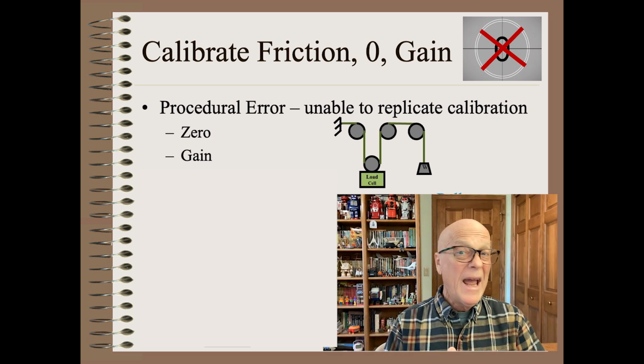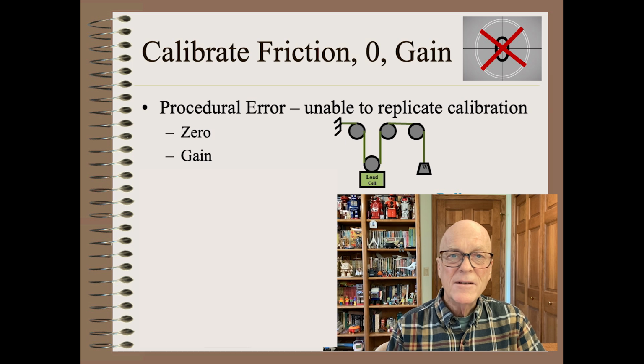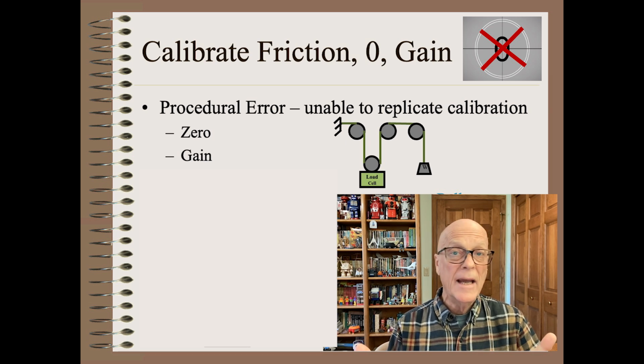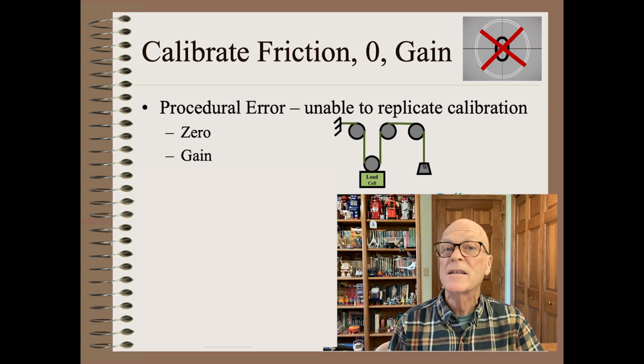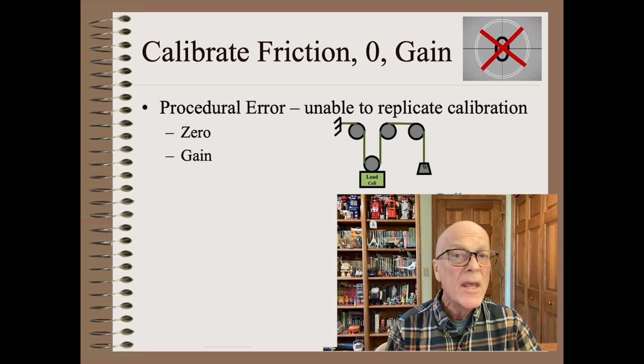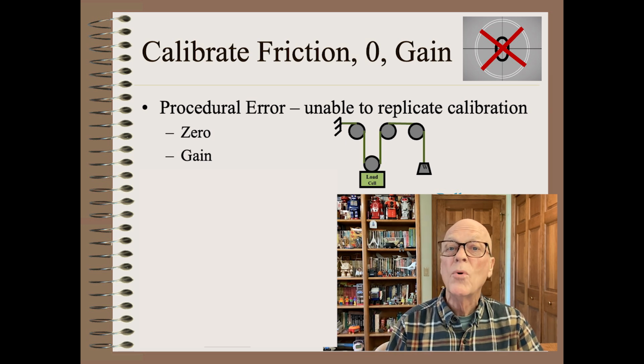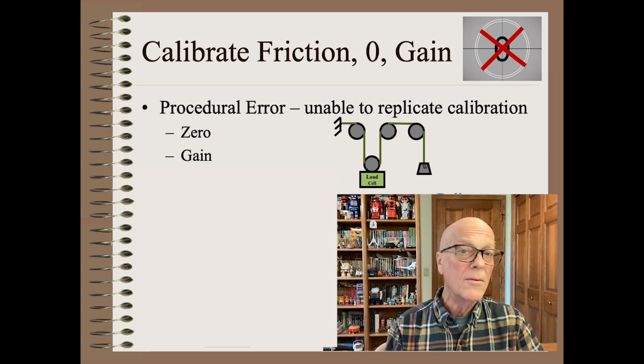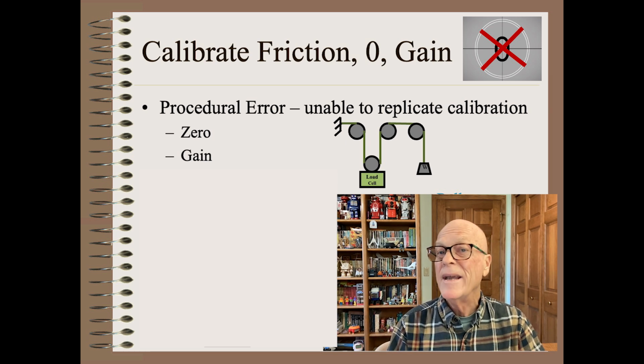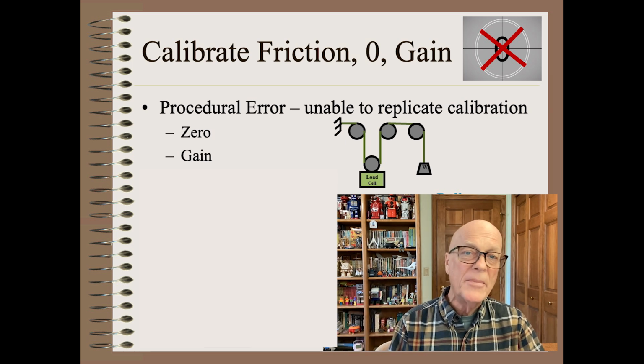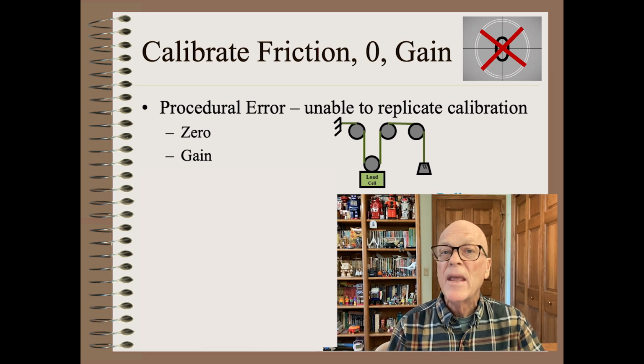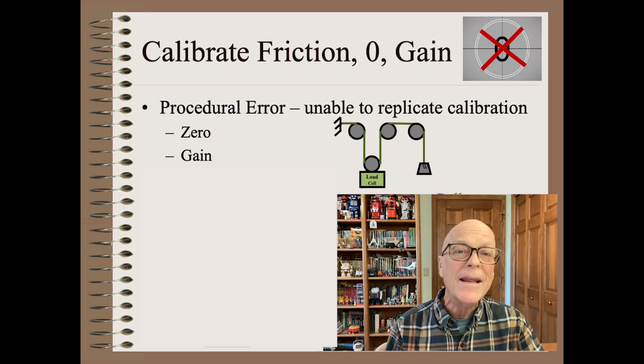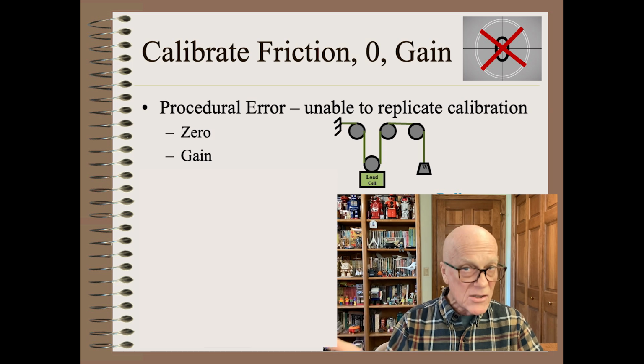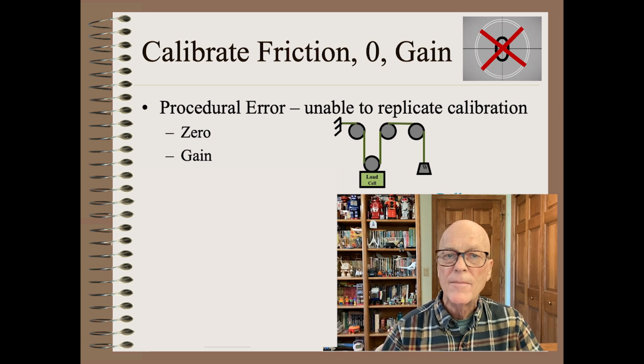Without going into application-specific details, we note that load cells are calibrated by hanging weights on a strap that follows the web run in that local area. We first set the zero with a weight set at zero. Then we hang a weight near the maximum rating of web tension or the load cell, and then we set the gain. Finally, we take the weights off and recheck zero.